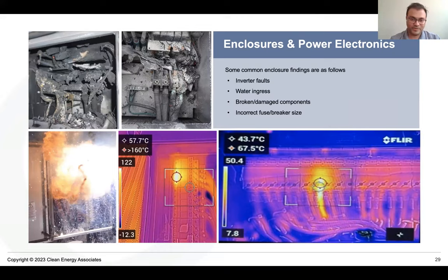Yeah. And Chris, to add to that, apart from loose screws, I have seen the technicians on site stripping off the wires right above the terminal blocks. When they strip off the wires right above the terminal blocks, there are small copper strands that go inside the terminal blocks. And we have seen a thermal event occurring from a small copper strand that went inside a terminal block. Simple things, the best practices, like don't strip your cables right over the terminal blocks. It's important. You may not notice the effects or the issues right when you are doing the work, but it can turn into a major fire.